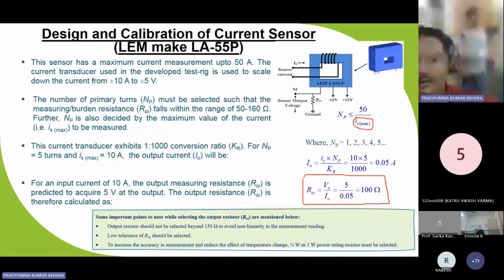In our system, we have used a 100 ohm burden resistor for the current sensor. There are certain important points to take care of while designing the current sensor. If you go through the data sheet, the output resistor range will be mentioned as 50 to 160 ohm. So one important thing is that you should not go beyond 150 ohm, in order to avoid nonlinearity in the measurement reading.